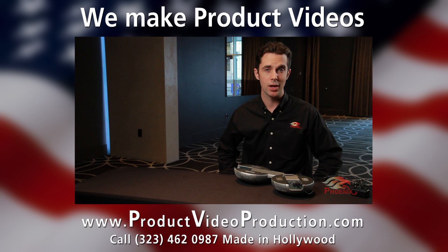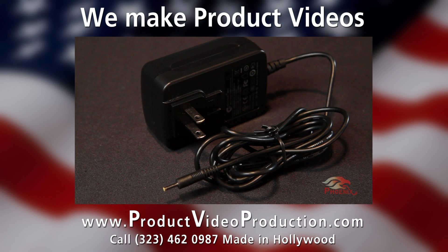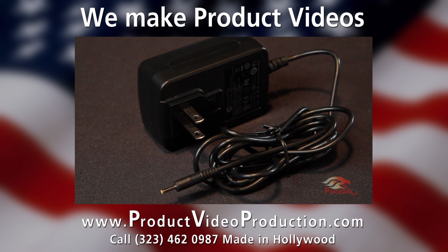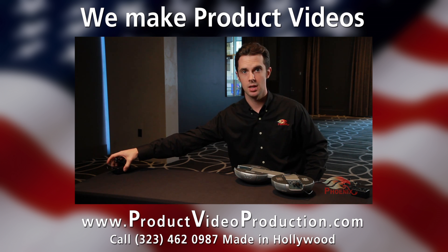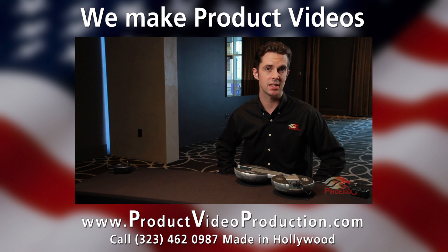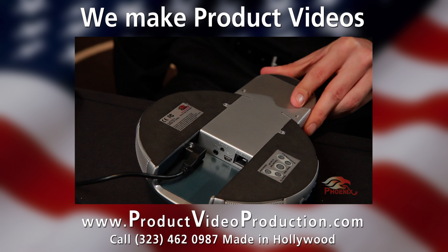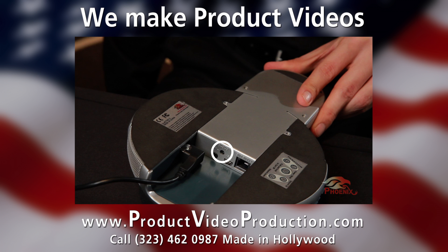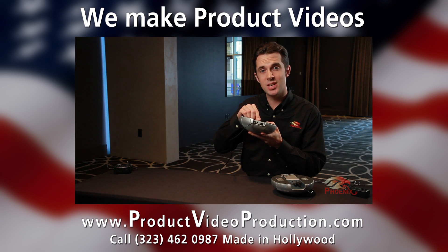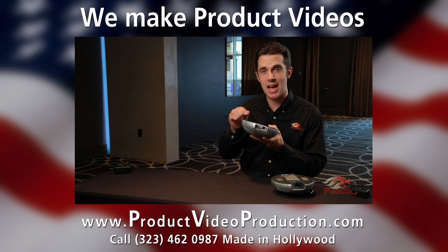How do we use the central power scheme? This option requires that you have a Phoenix Audio 48-volt power adapter. All the units participating in the chain also need to have an interface card to support it. If your Quattro has any communication interface like the telephone or smartphone, it already supports this option. If it does not, it has to have a power chain card called the 304. If you look at your Quattro connectors, you should be able to locate a small DC connector between the USB and the 3.5 millimeter connector. If your unit does not have such a connector, it does not support the power chain option.